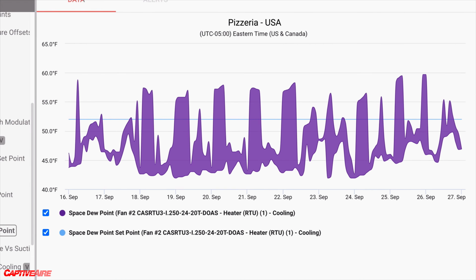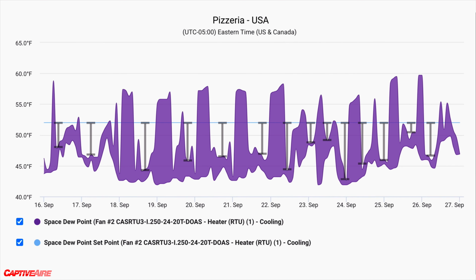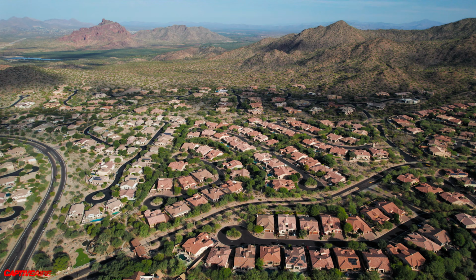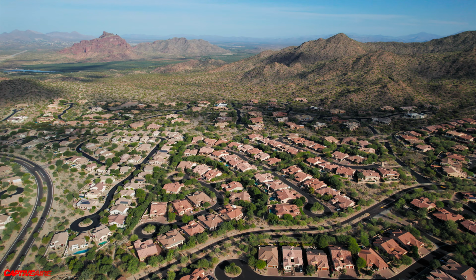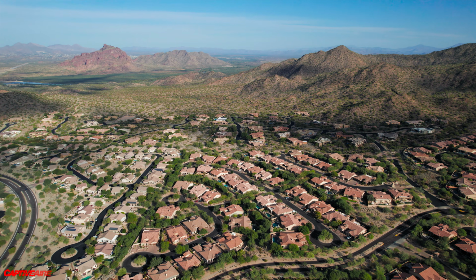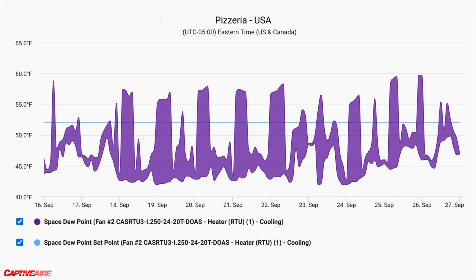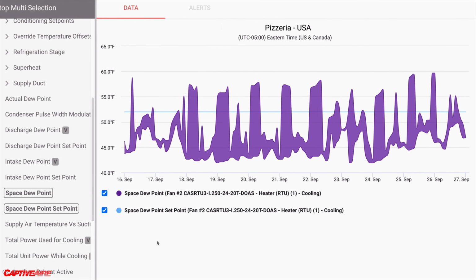Note here that the space dew point inside the building is often way lower than the set point of 52 degrees, and by some margin. If this is because we're over dehumidifying, this would be a huge energy waste. You could have times where we're below that space dew point set point because the intake is dry. If you're in a climate where it's very dry, that's not an issue, but we want to make sure we're not causing that dew point to be below the set point because we're running our compressor more than we need to.